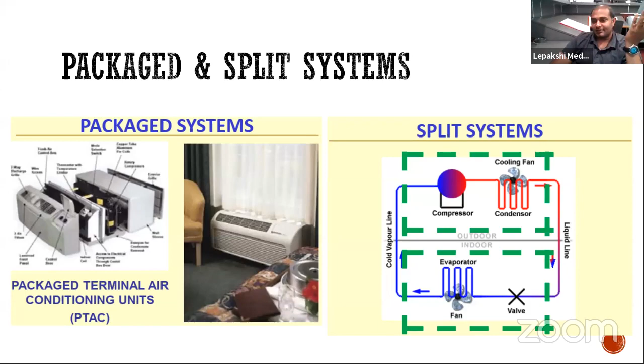Towards the right, you have the split system. As the name says, what is a split system? You have the compressor and condenser in one portion and the evaporator and expansion valve in another. These split systems you can see a lot these days too. There will be a condenser on the outside, and you run the refrigerant lines - a suction line and a liquid line - from the condenser to the evaporators, which are inside those cassettes. They can be wall mounted or ceiling mounted. These are more popular, but they have their own limitations. You can't use them in a 20 or 30 story building because they're going to take up all the space - where are you going to put the condensers and all that stuff?